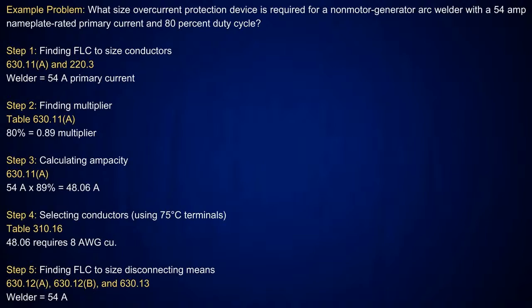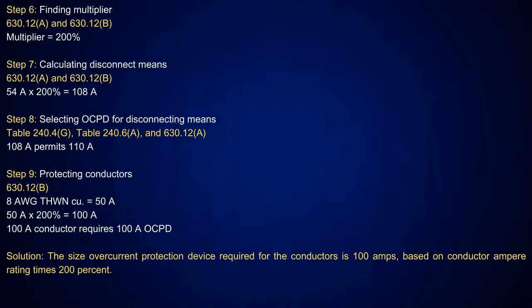So in here, I'm going to size the conductor, which is a number 8 conductor. I go over, look at table 310.16, and I pick that up for the 75 degrees C column. The next size above 48.06 amps is 50 amps, which is number 8 conductor. Now I'm going to look at sizing the overcurrent protection device. So I'm still going to use the nameplate of 54 amps.